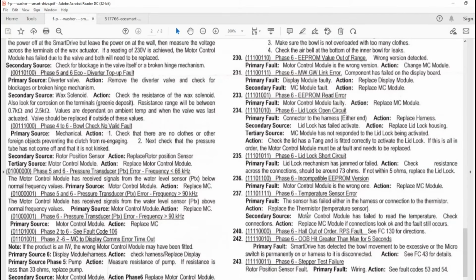Temperature sensor error. There's a few different temperature sensor errors. This one's the only one mentioned here by the look of it, but they are usually to do with it going higher than 100 degrees or lower than 0 degrees. Of course, going higher than 100 degrees means your water's boiling. That's not usually going to happen. Lower than 0 can happen if you've got something outside and the water's starting to freeze. But if the sensor's slightly out of calibration and it starts to freeze, the motor controller will start throwing errors, in which case you can replace the sensor, or you just got to get it somewhere warmer.